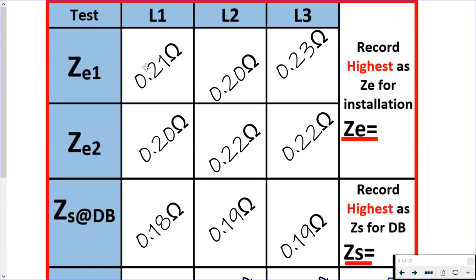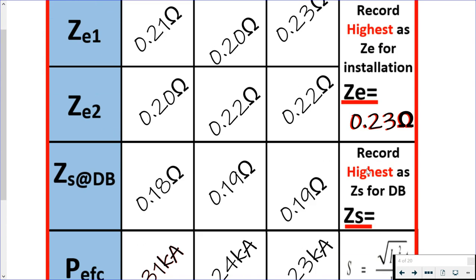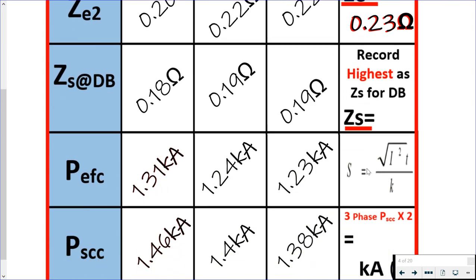You'll see there we have carried out six earth fault loop impedance tests: two on line one, two on line two, two on line three. The highest of which as we can see here is 0.23 ohms, so that's the one that we would record on our certificate and our condition report.